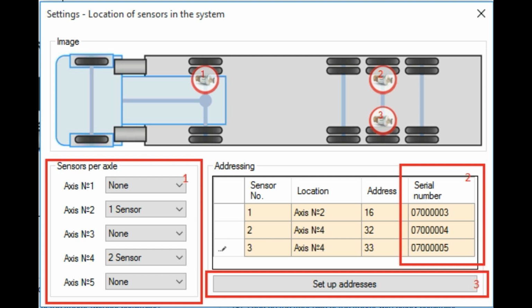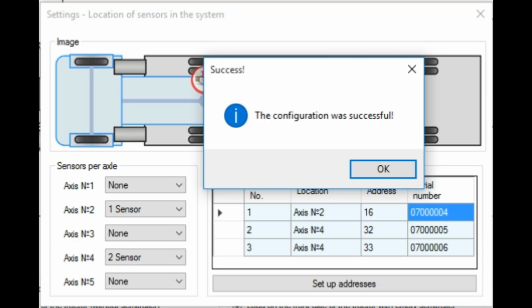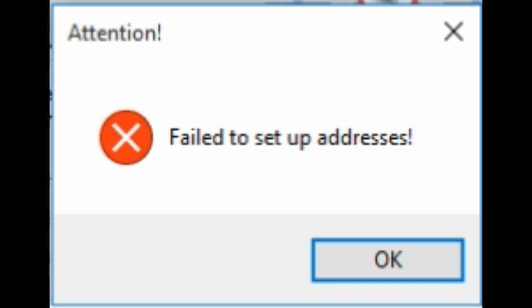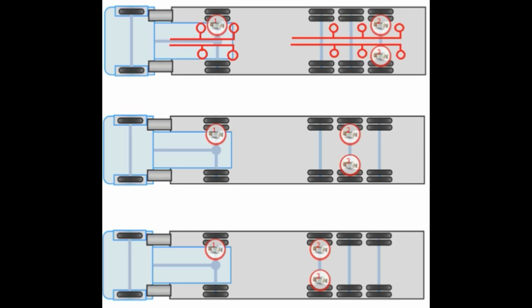Then, in the addressing table in the serial number column, enter the serial numbers of Eurosens Difference T configuration blocks according to the location and click on the Setup Addresses and Load Parameters button. In case of successful setting of addresses and loading of parameters, the corresponding dialog box will be displayed. In case of an error in setting of addressing and loading of parameters, an error message will be displayed. This can occur if not all configuration blocks are correctly connected or serial numbers are entered incorrectly.